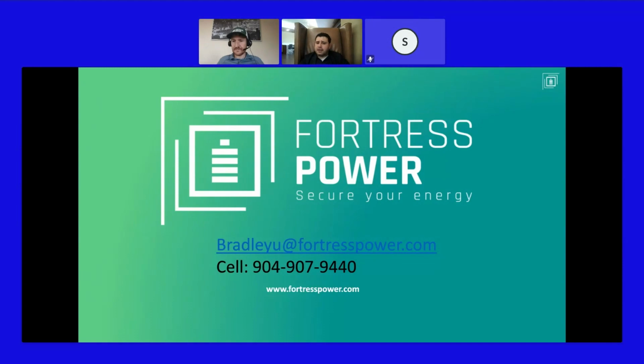Is the BMS using active balancing, passive balancing, or other? It is using passive balancing. Yes, it's using passive balancing. Your smart energy panel and inverter have different maximum elevations. That could be the case because the elevation limitation comes from the different cooling. The higher you go in elevation, the less atmospheric cooling effect you get because the air density goes low. So when I said 13,120, I think I was referring to the battery. Let me check that. Okay, 13,120 is for the inverter, and for the battery, let me take a look.